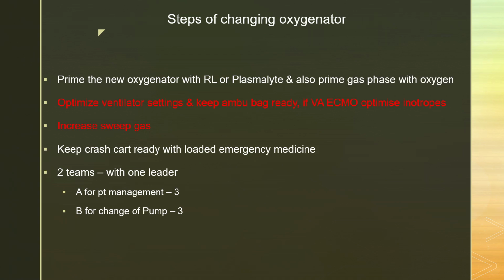Now increasing sweep gas will get the CO2 down. Okay. It was basically 40, it might get it down to 30 or 25. That might give you 2 to 10 seconds extra, nothing more than that, but it might give you a few seconds extra, so that if you take a little more time to change the oxygenator, that might help you. Okay. So when you start priming, you go up on the ventilator settings, at the same time increase the sweep gas to 1.5 times. So that might give you some more time for change of components. Okay.